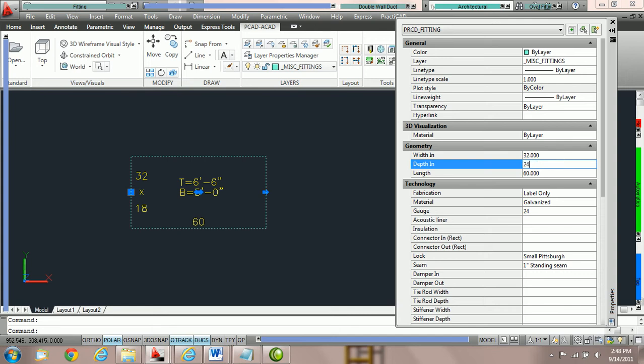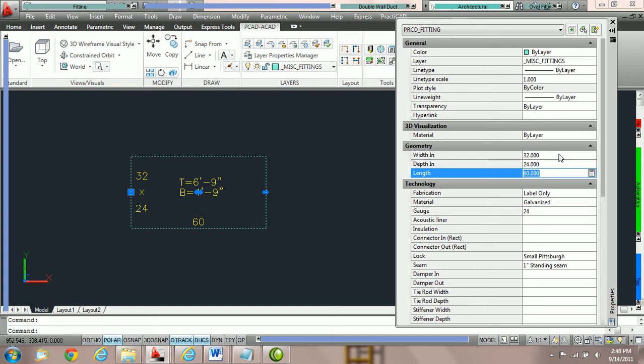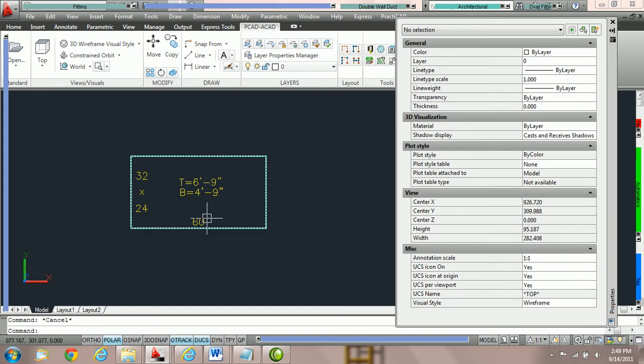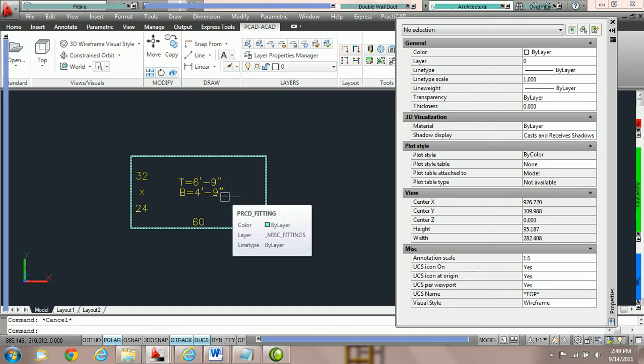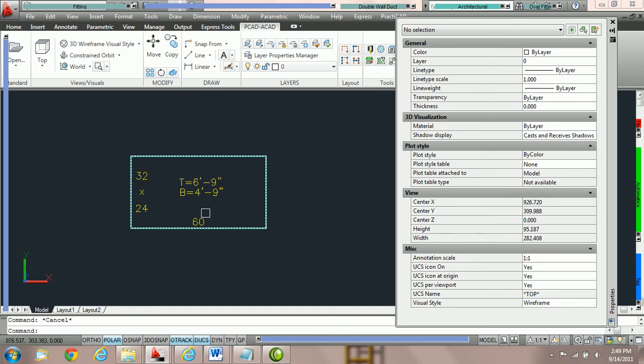Here we're going to take depth and type in 24 inches and hit Enter. You can notice that the duct is changing and the tags are changing along with it, including elevation tags. The duct line grows from the center line of duct, so when we change the depth, the duct's depth changed above and below the center line.